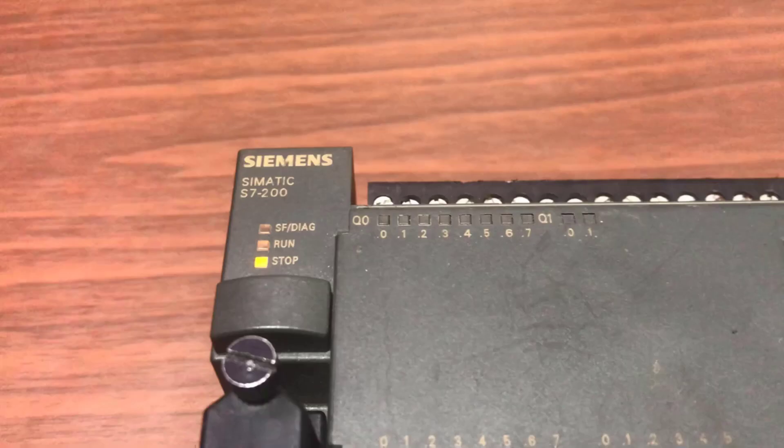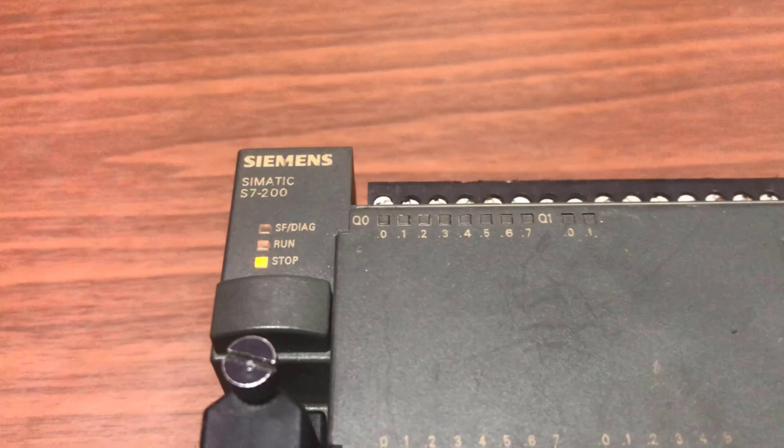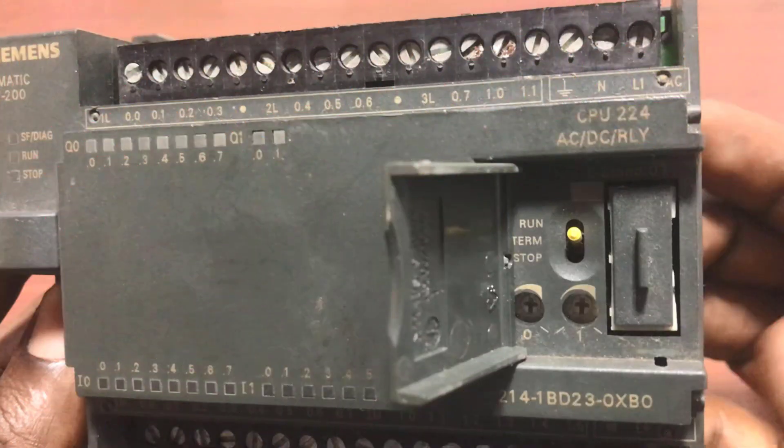Here are some few tips about this PLC. The stop LED is always yellow when the system is in stop mode. And whenever you download a PLC program, the PLC will move into stop mode and you need to restart it by using the selector switch or you can do it from the software interface.